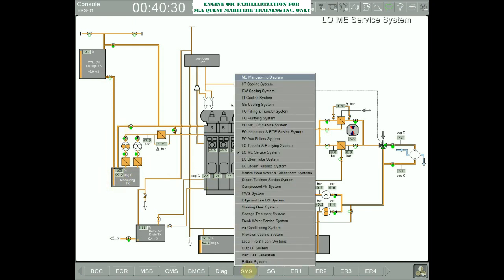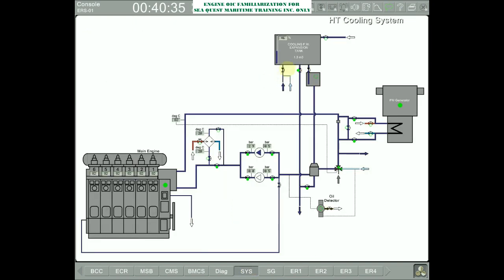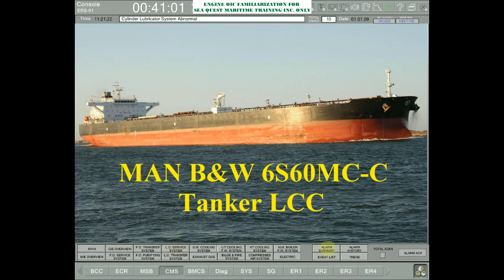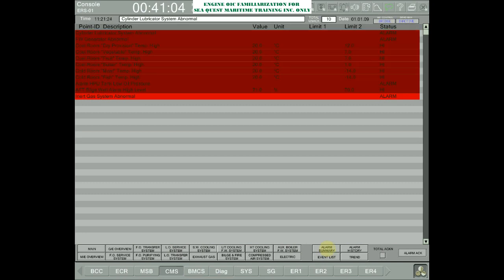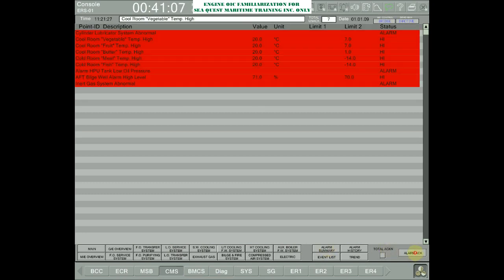Then we go to SYS. Let's check the HT cooling system. Expansion tank level still at 46%. Maybe we can add some more there up to, let's say, 60%. Okay. So while we are waiting for that, let's go to CMS and click summary and acknowledge all alarms.